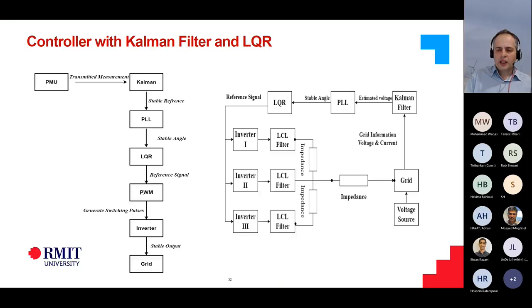As I mentioned, we developed the controller based on phasor measurement units, which rely on measurements across different parts of the network that go through the Kalman filter. That Kalman filter provides stable reference points for the PLL, the PLL then feeds into the LQR, and we have PWM signals going through the inverter, with the inverter providing the signal to the grid.